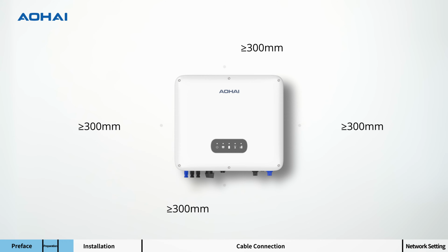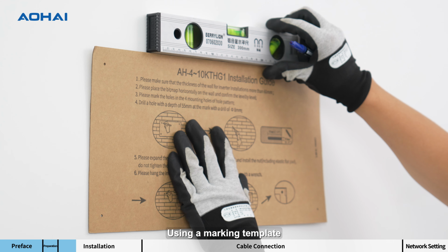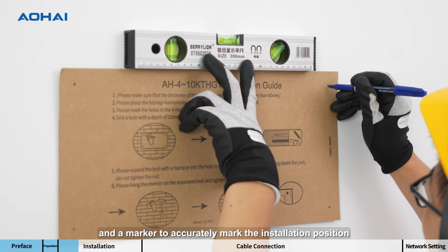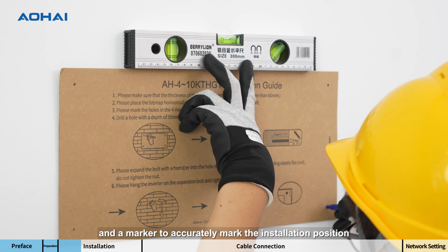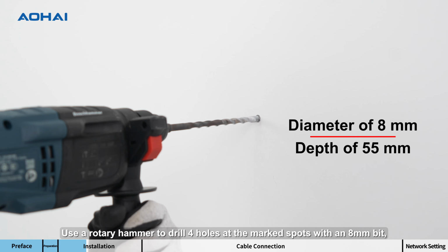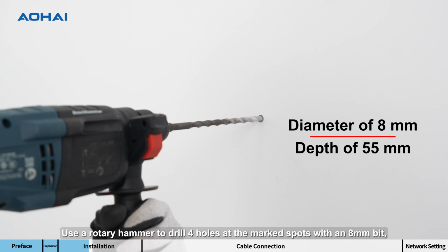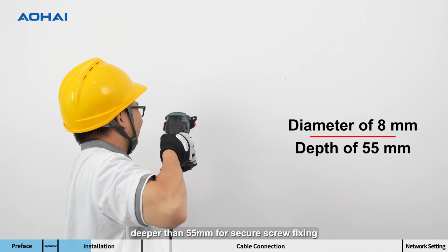Before setting up the inverter, find a spot that can hold its weight and has enough room. We suggest keeping 300 mm clear around and above it for good cooling and easy setup. Using a marking template, combine it with a level and a marker to accurately mark the installation position on the wall. Use a rotary hammer to drill 4 holes at the marked spots with an 8 mm bit, deeper than 55 mm for secure screw fixing.